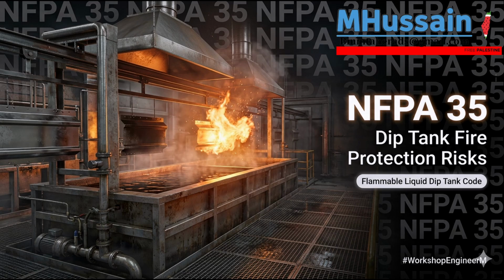That sounds almost as expensive as just buying more land. Sometimes it is. You know, I noticed another really fascinating clause that dictates layout based on emergency response. The code mentions something called protection for exposures. Yes. And if you don't have this protection, your setback distances for unstable liquids automatically double. What exactly are they asking the owner to prove here? So protection for exposures is essentially the NFPA's way of asking, is the cavalry coming? It means you have a public fire department or a highly dedicated private fire brigade capable of arriving quickly and laying down heavy cooling water streams to protect the adjacent neighboring properties from the radiant heat of your burning facility.